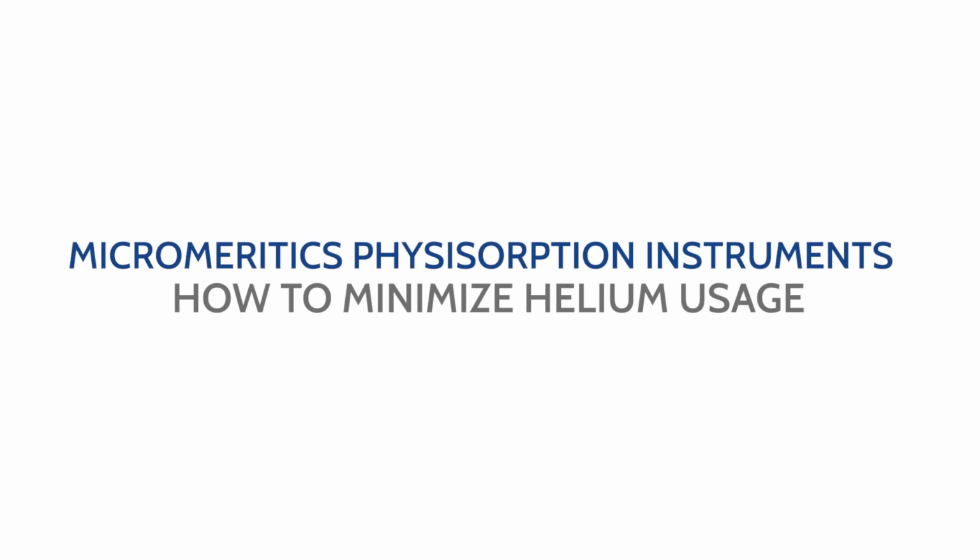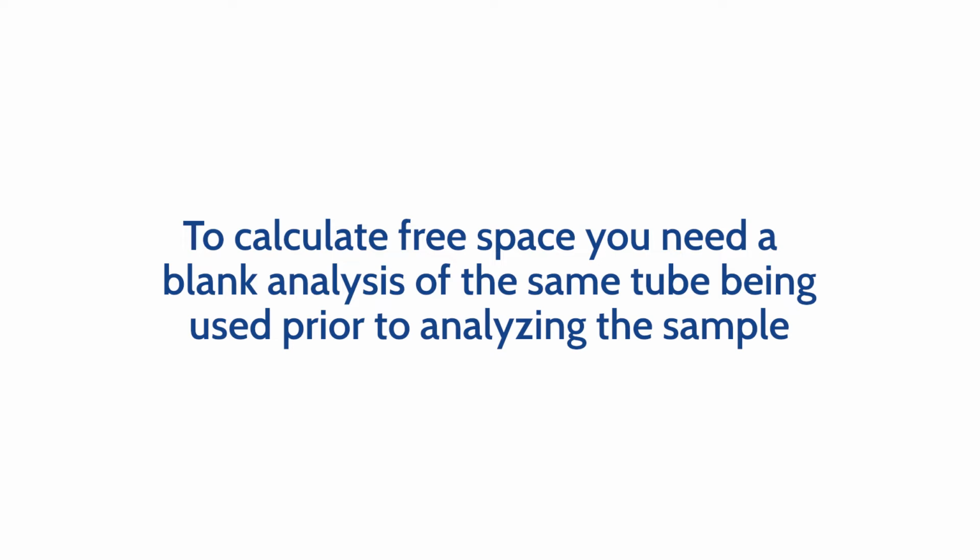This video will show you how to minimize helium usage by calculating the free space from a calibrated blank tube rather than measuring the free space for each analysis on Micromeritics Physisorption instruments.